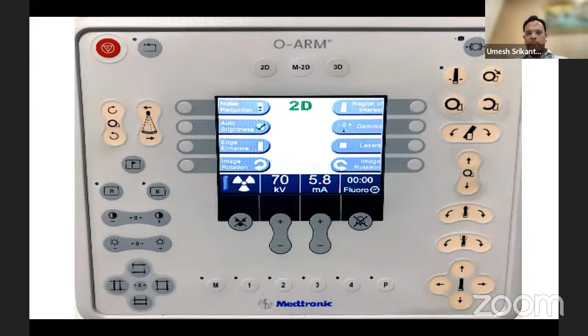So for example, in this, we have multiple selection options. You can select the dosage, you can select the thickness of the patient, and you can select whether you want the scan in a low dosage radiation, a standard dosage, or a high definition dosage, HD dosage, depending upon what you are trying to image. For example, in osteoporosis, obese patients, or where prior implants are already there, you can select a high definition scan where the resolution will be more, but the radiation is also more. For a thin patient, a routine case, not a deformity, you can always select a low radiation dose, which can give a relatively good quality image, as I'm going to show, but with reduced radiation exposure to the patient as well. In addition to that, you can also select the patient thickness.